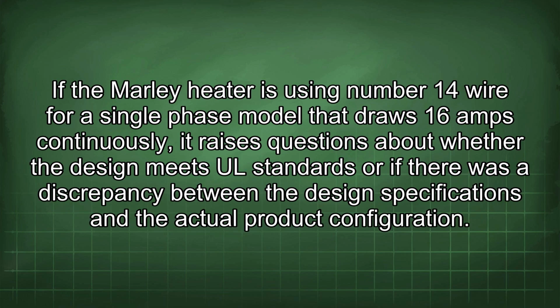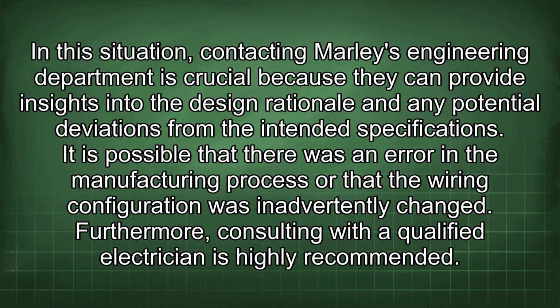If the Marley heater is using number 14 wire for a single-phase model that draws 16 amps continuously, it raises questions about whether the design meets UL standards or if there was a discrepancy between the design specifications and the actual product configuration. In this situation, contacting Marley's engineering department is crucial because they can provide insights into the design rationale and any potential deviations from the intended specifications. It is possible that there was an error in the manufacturing process or that the wiring configuration was inadvertently changed. Furthermore, consulting with a qualified electrician is highly recommended.